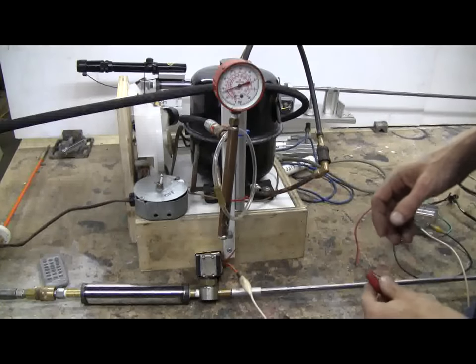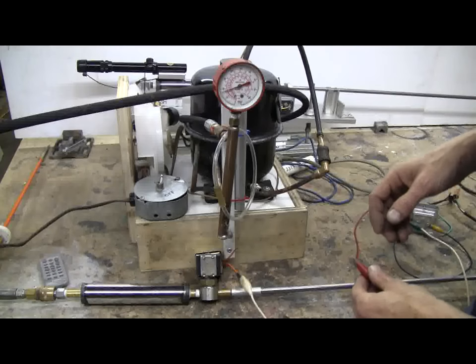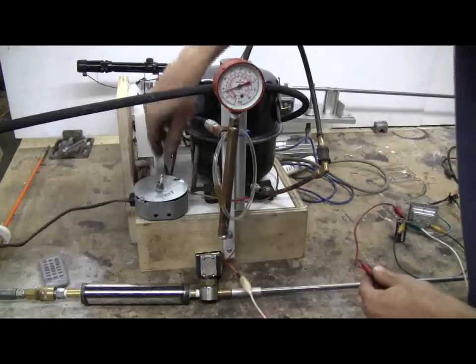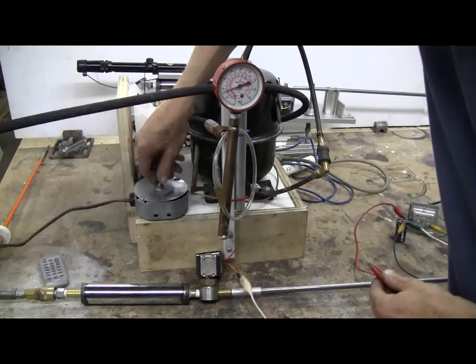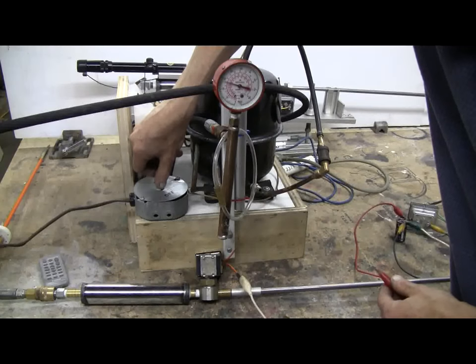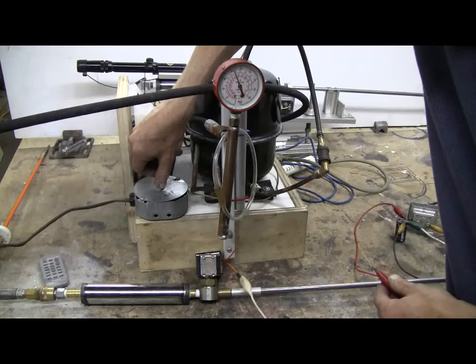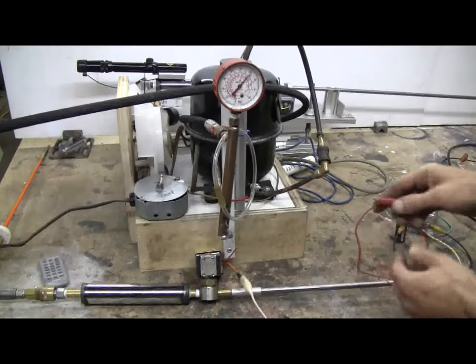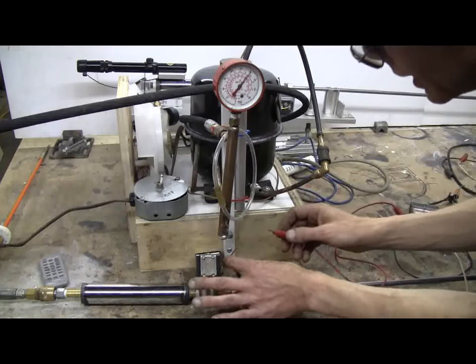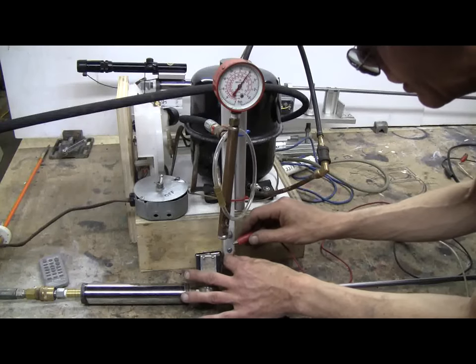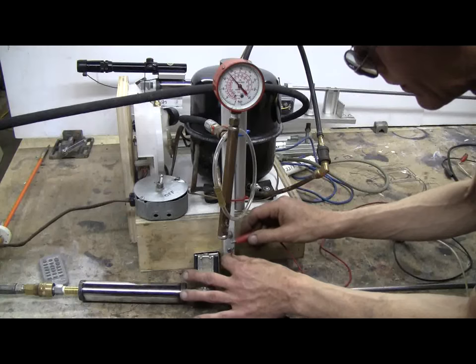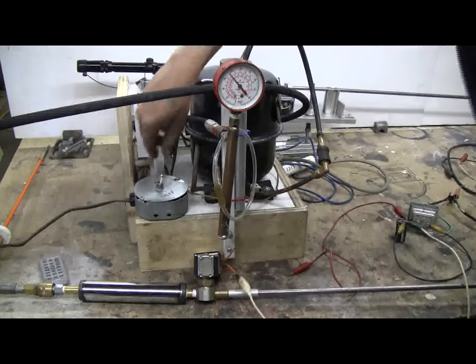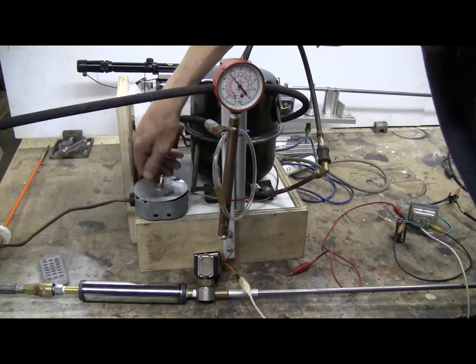Now that we're set up to use DC to fire the solenoid, I'm going to bring the pressure up to 300 pounds. 150, 200, 250, 300 psi. We could not fire it here on AC before. Here goes DC. Immediate firing.